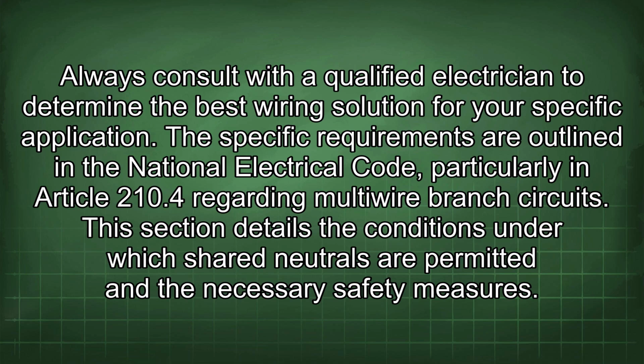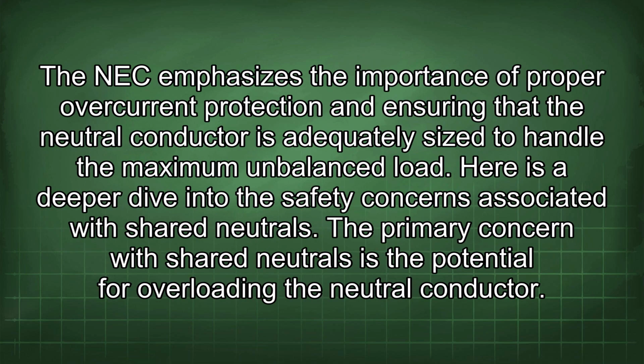The specific requirements are outlined in the National Electrical Code, particularly in Article 210.4 regarding multi-wire branch circuits. This section details the conditions under which shared neutrals are permitted and the necessary safety measures. The NEC emphasizes the importance of proper overcurrent protection and ensuring that the neutral conductor is adequately sized to handle the maximum unbalanced load. Here is a deeper dive into the safety concerns associated with shared neutrals.